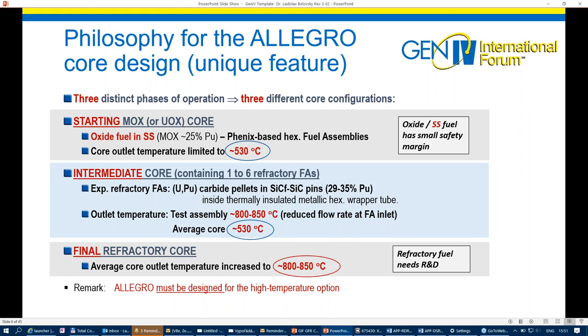After mixing with the coolant from the driver core fuel assemblies, the average core outlet temperature of the primary helium will be again limited to roughly 530 degrees C. And when having the refractory fuel well proved for full scope operation, then the final full refractory core will be loaded and Allegro will be able to be operated at the target temperature around 800 degrees C. It means that all the technology around which can't be replaced must be designed from the very beginning for the high temperature option.